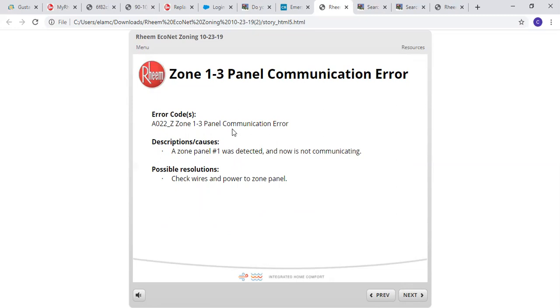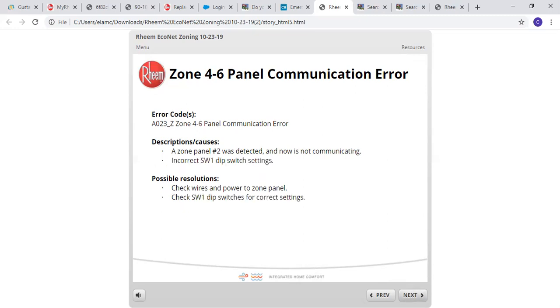Zone 1 through 3 panel communication error. A022Z, zone 1 through 3 panel communication error. The description and cause: zone panel 1 was detected and now it's not communicating. So in a case like that, you want to check all your wires and power to that zone panel. Zone 4 through 6 communication error, same thing. Some other causes: zone 2 was detected, now it's not communicating, or you could have an incorrect SW1 dip switch setting. Resolutions: check wire and power to the zone panel, and then check your SW1 dip switch to ensure you have the correct setting. So in this case here, if you have a second panel for your 4 through 6 and you don't turn on dip switch 1, you very well could end up with this exact communication error.